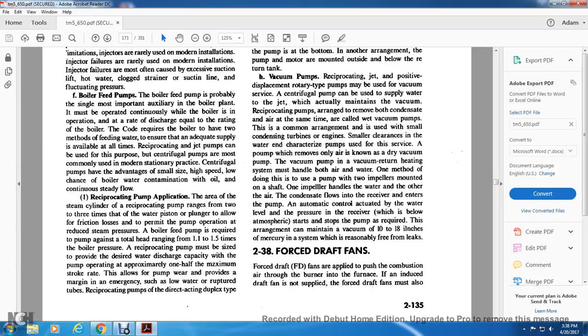The code requires the boiler to have two methods of feeding water to ensure an adequate supply is available at all times. Reciprocating pumps can be used, but centrifugal pumps are most commonly used with modern stationary practice. Centrifugal pumps have the advantages of small size, high speed, low chance of boiler water contamination with oil, and continuous steady flow.